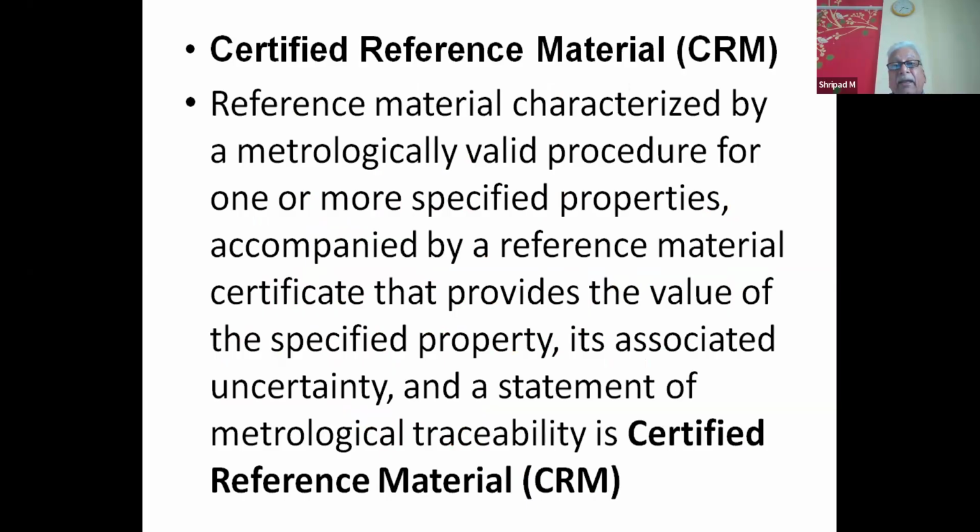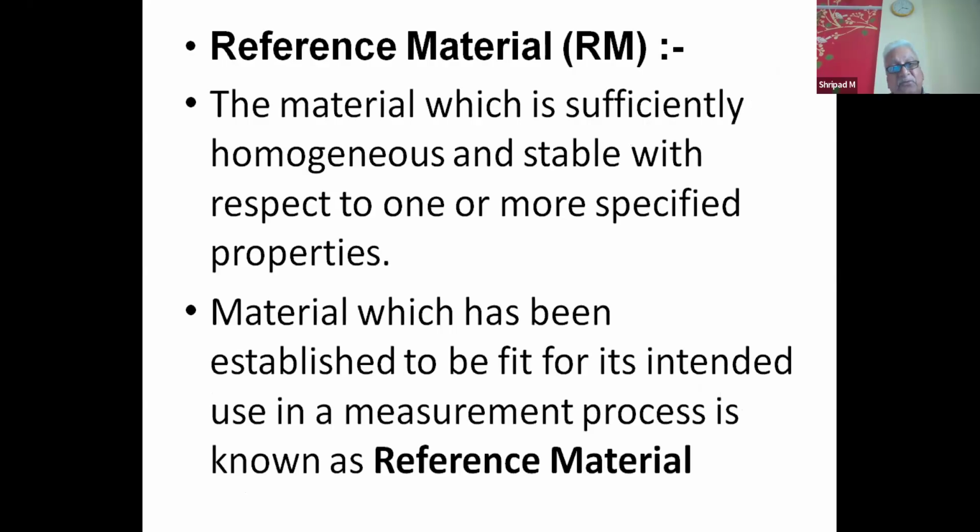A reference material characterized by a metrologically valid procedure for one or more specified properties, accompanied by a reference material certificate that provides the value of the specified property with its associated uncertainty and a statement of metrological traceability, is known as certified reference material or CRM. It is a reference material, but having some unique characterization, unique traceability, unique properties.